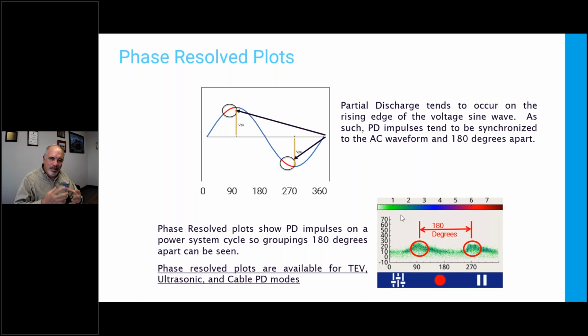Phase resolve plots are the number one thing. If you're ever considering buying equipment and it doesn't have a phase resolve plot, you should really think about that hard. PD occurs in this part of the sine wave. As you're leading up to the peak, it would make sense. As I get to the peak voltage is where the field's the strongest.